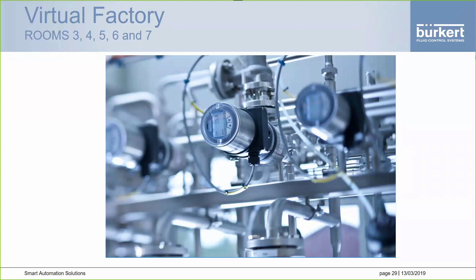There are several significant advantages to using a decentral automation concept. I think one of the biggest points of failure is the risk of moisture or condensate ingress. So a lot of R&D effort has gone into specifically designing devices for continued operation in wet and washdown areas. And the nice thing is it also eliminates any risk of condensate issues as well. The ability to significantly reduce tubing and cabling requirements is a massive factor that needs to be considered. Using an intelligent valve top, the decentral automation concept only requires one electrical connection and one compressed air connection.